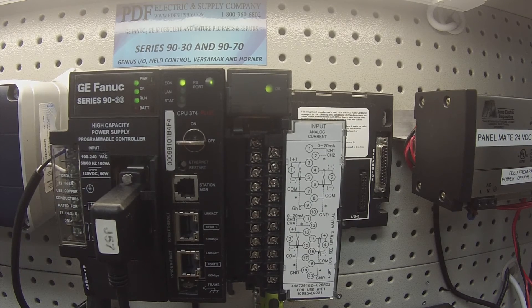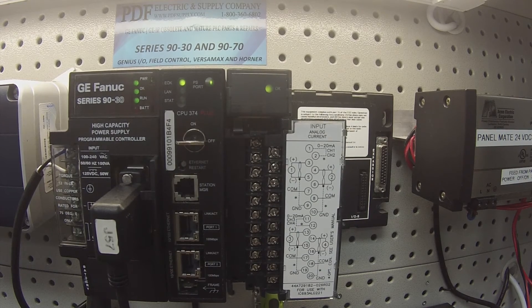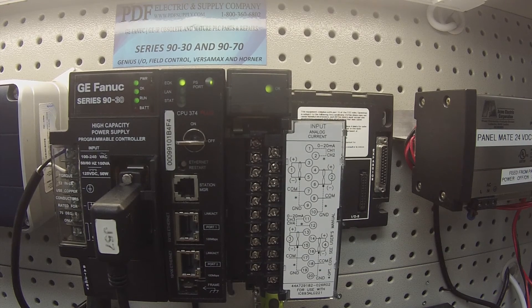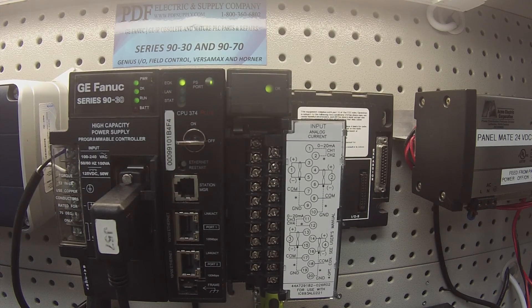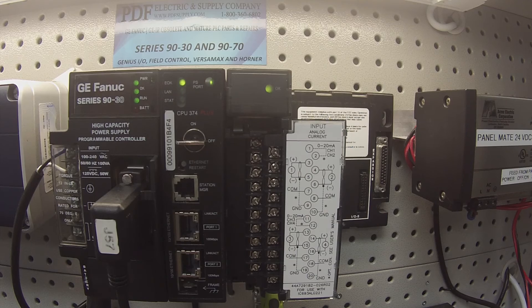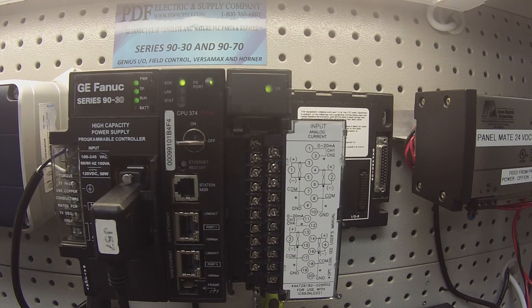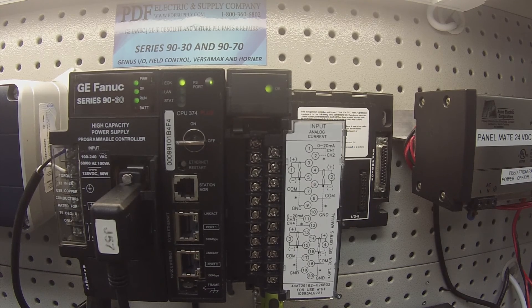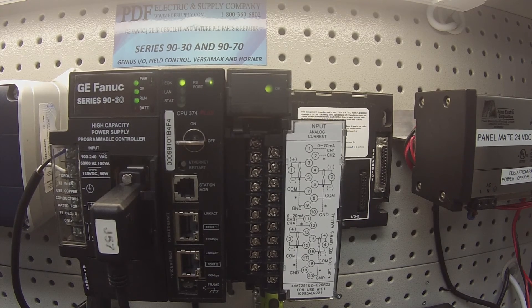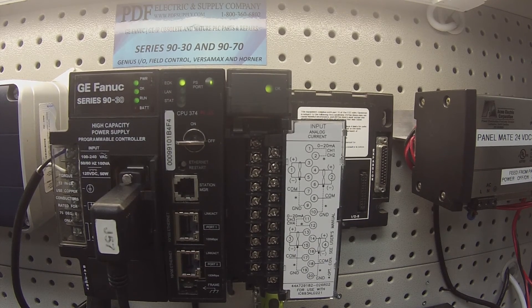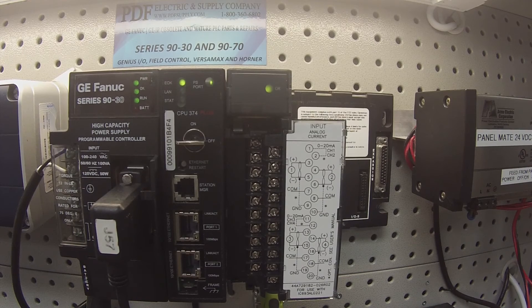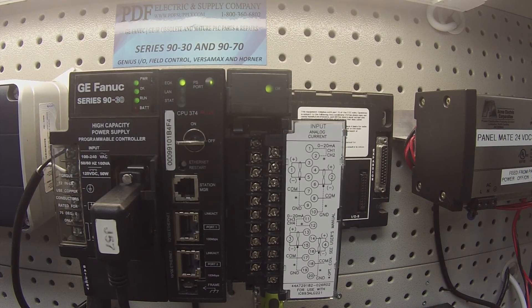If you still think there's a problem on one of the channels, you can go up and down with the reading. Maybe bring it closer to 4 and then dial it up to 20 milliamps to see that you have the proper range that the device is supposed to be able to give you.